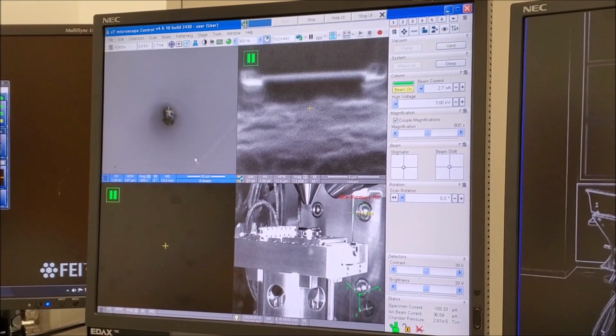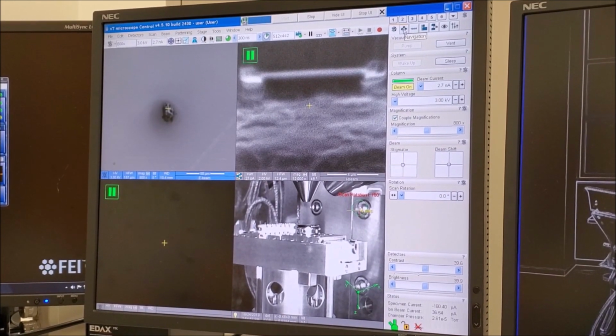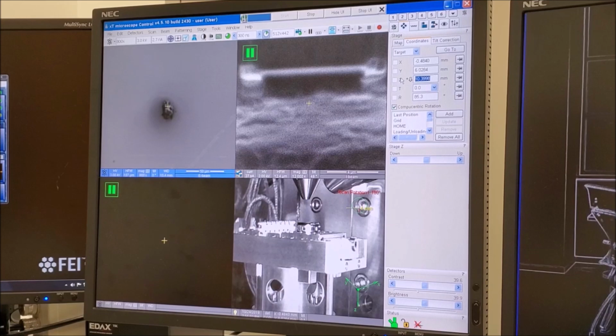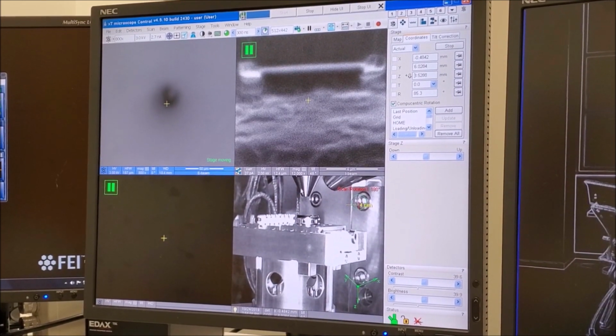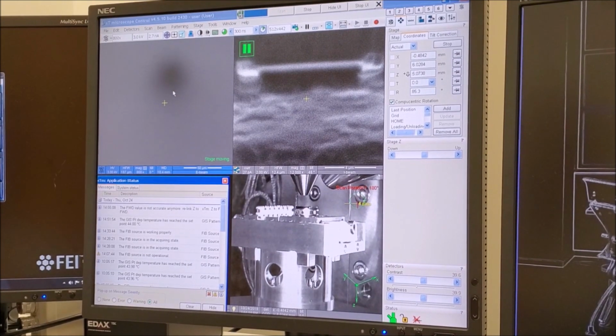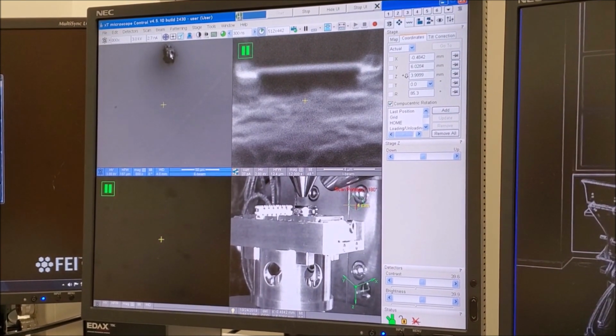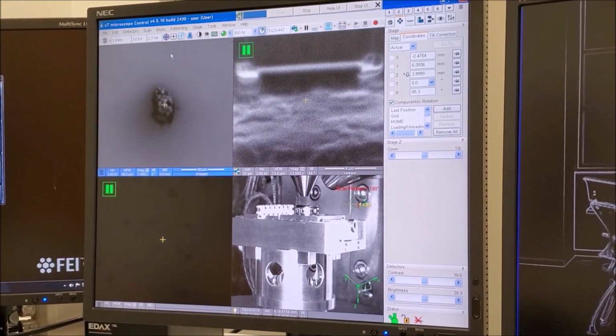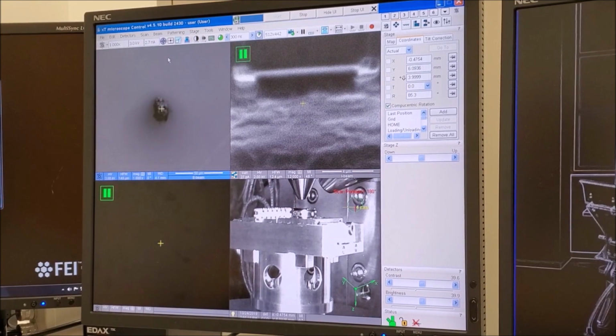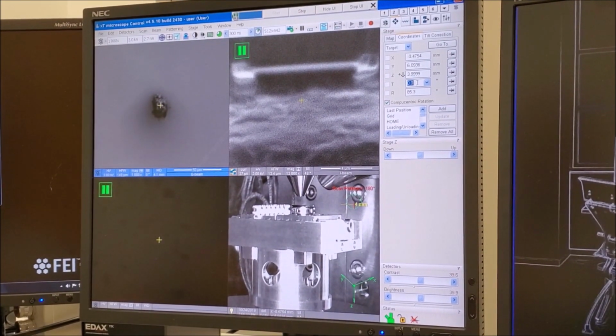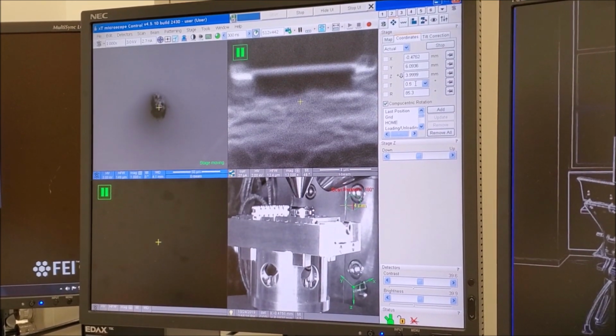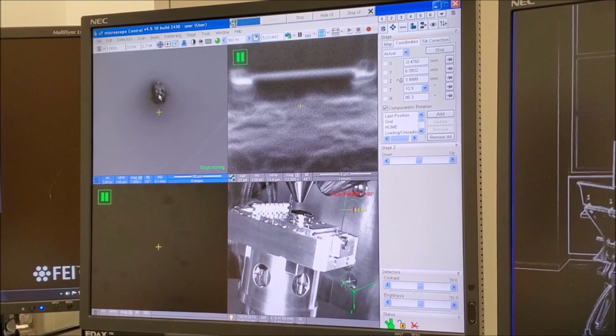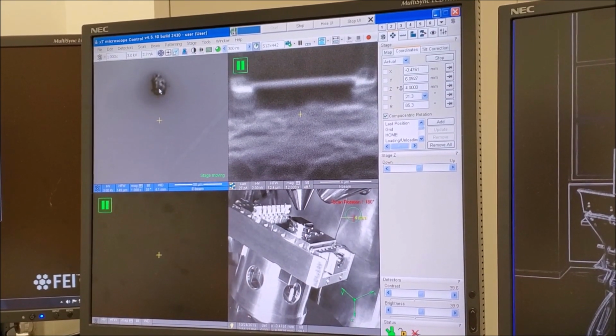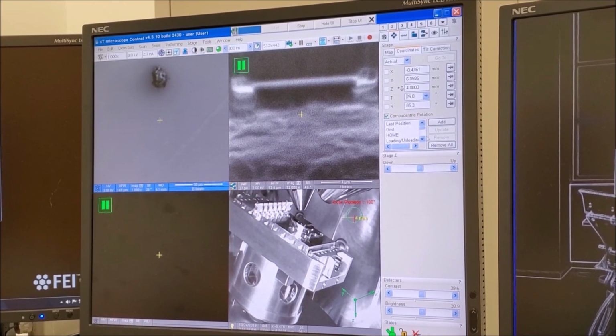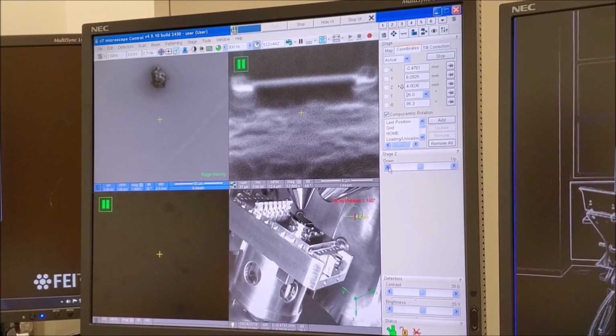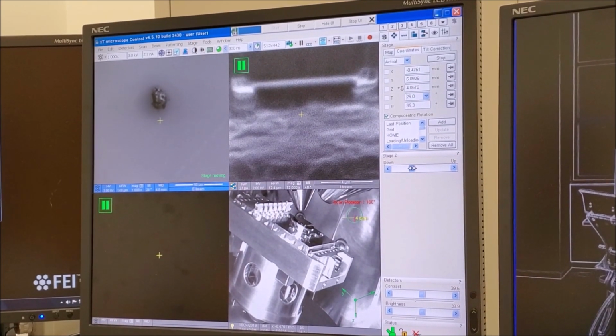Verify that the electron beam is focused with Z linked to the working distance. Enter the navigation module and enter 4 in for Z to move the stage so the working distance is approximately 4 millimeters. Find a recognizable feature on the surface of the specimen and move it to the center of the image. Then tilt the stage to 26 degrees and note which way the feature moves away from the center of the image as the stage is tilted. In this case, the feature is moving up, which means that the stage needs to be brought down to bring the feature back to the middle of the image. Do this by adjusting the stage Z control, in this case to the left, to move the stage down and bring the feature back to the middle.